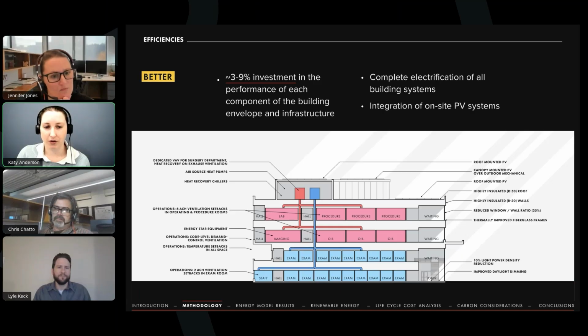The other big change for the mechanical systems is that in the better option, we've segregated some of the areas. So we now, instead of that one big VAV with reheat air handler, we have segregation between the MOB, which has an urgent care that has longer operating hours than the normal office areas. So the office areas would run sort of 7 a.m. to 7 p.m. and urgent care is 6 a.m. to midnight. So when we segregate those air handler systems, we can more effectively turn off the main MOB air handler at 7 p.m. And so that results in energy savings.